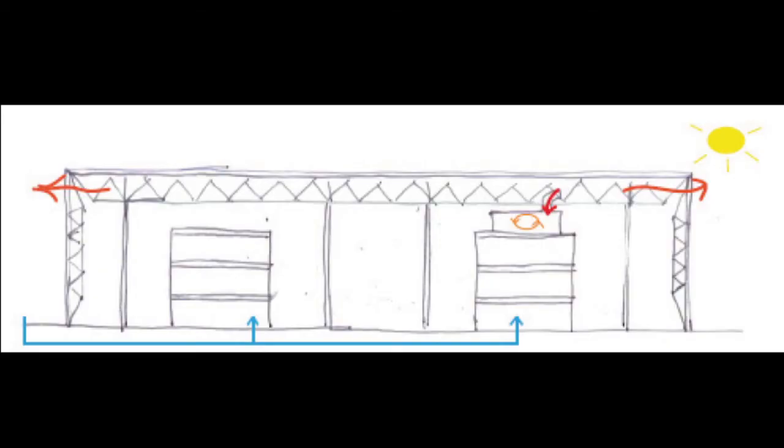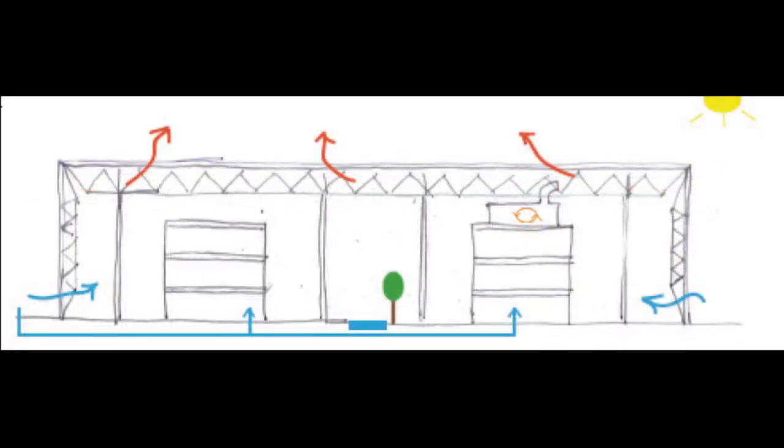The air flows in through the underground air ducts and is preheated in the winter before it flows into the units. The building units have a heat exchanging compartment on top. Here, the exhausted air which flows into this compartment exchanges heat with the air of the buffer space. In the summer, it's pre-cooled.